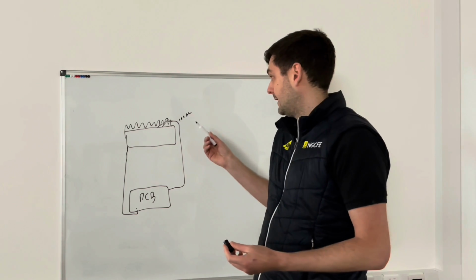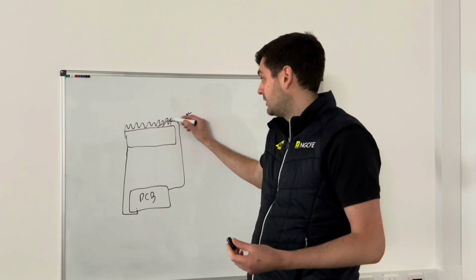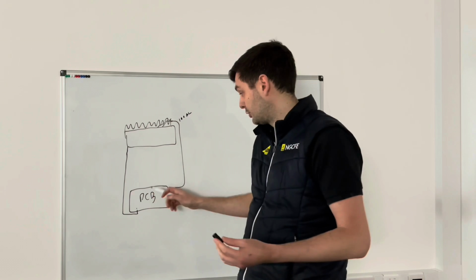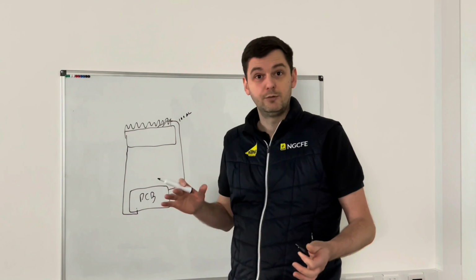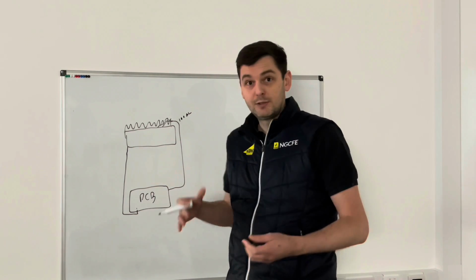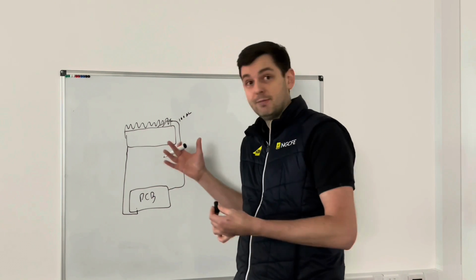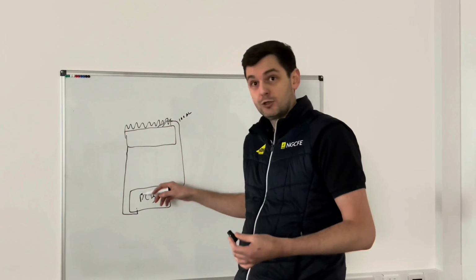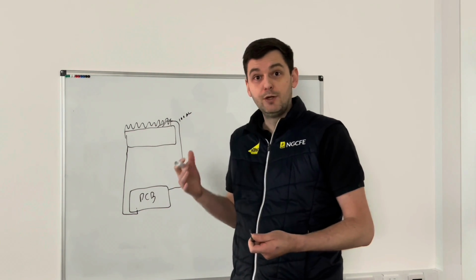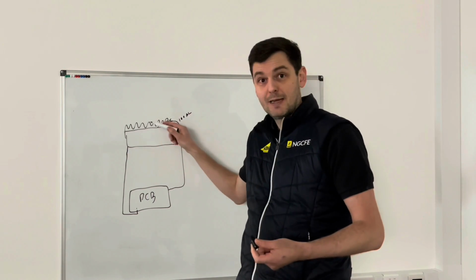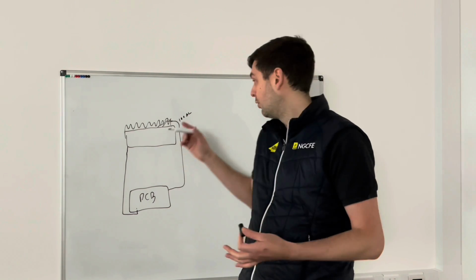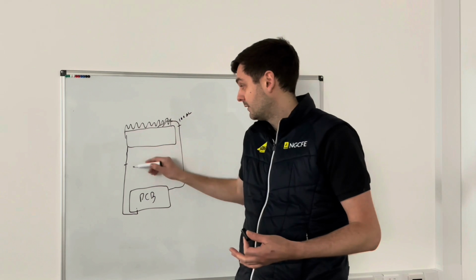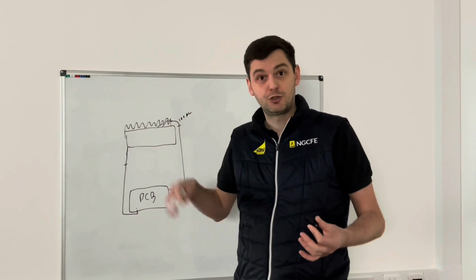So if we imagine that the voltage here, its sole purpose, all it wants to do is go back to the board. That's all it wants to do. And when it gets back to the board as DC current, we know that there's a flame there. If for whatever reason the board loses the DC current, then we know that there's an issue. Either the flame's not established, the flame's extinguished, or there's a break somewhere and the circuit's lost its continuous loop.